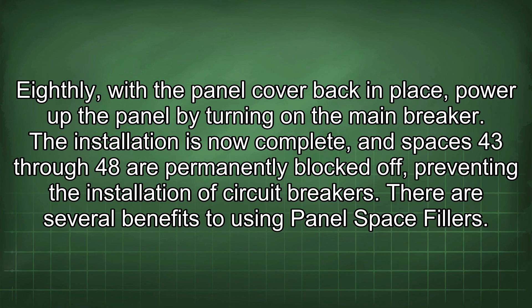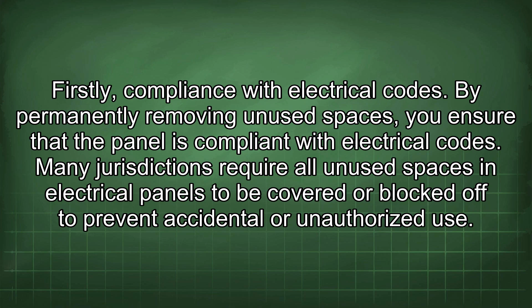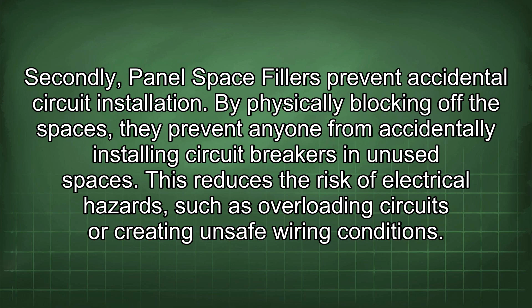There are several benefits to using panel space fillers. Firstly, compliance with electrical codes. By permanently removing unused spaces, you ensure that the panel is compliant with electrical codes. Many jurisdictions require all unused spaces in electrical panels to be covered or blocked off to prevent accidental or unauthorized use. Secondly, panel space fillers prevent accidental circuit installation. By physically blocking off the spaces, they prevent anyone from accidentally installing circuit breakers in unused spaces. This reduces the risk of electrical hazards such as overloading circuits or creating unsafe wiring conditions.